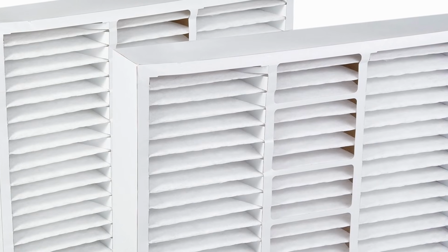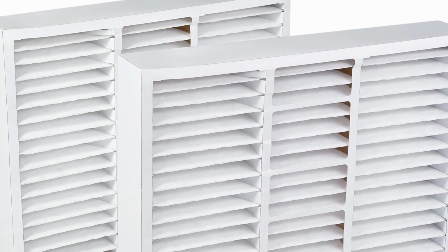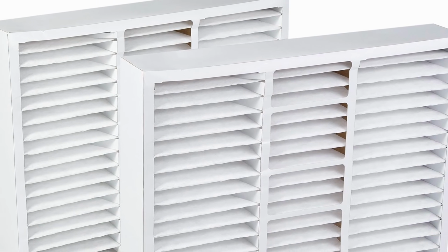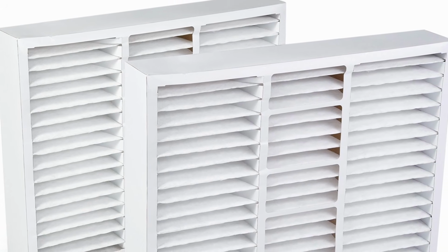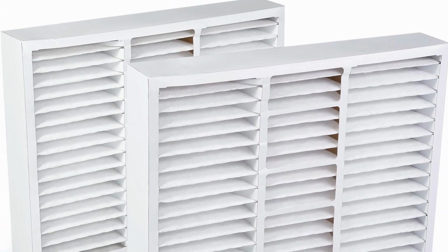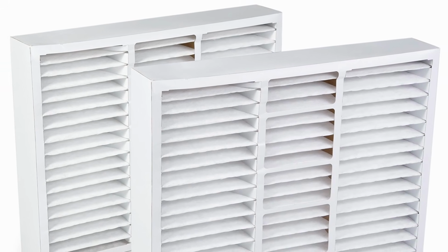Your AC air filter is not something that should be casually neglected, even though it is all too easy to forget. The HVAC filter should be replaced regularly in order to keep the inside part of the AC clean. If your air filter is clogged, it slows down the airflow and blower efficiency and will not supply enough air to the second floor. In addition, a coil can freeze up because of not the proper amount of airflow due to lack of maintenance.